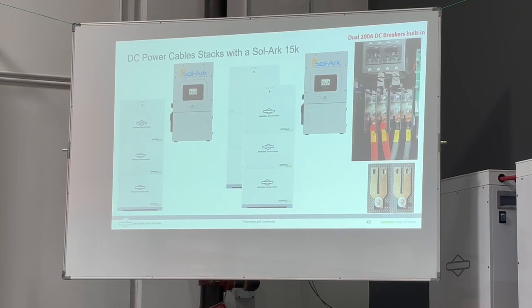just in free air. So there are plenty of installs, not so many in the US, but there are plenty of installs where they don't require your battery cables for low voltage batteries to be in conduit. I always put it in conduit because I like the look of it anyway. I think it looks better to have all your cables covered, right? But if you are doing it with exposed cabling, you can use these combiner bars and put them on the Sol-Ark. Otherwise, we just recommend for a single stack, use two sets of cable. For a double stack, use the two cables. And that's in the wiring charts as well.